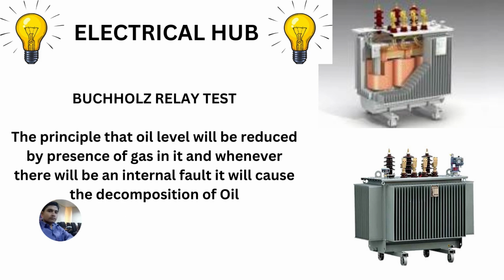Now, let us move towards the Buchholz relay test. Before knowing the test of the Buchholz relay, we should know the operation of the Buchholz relay. How does the Buchholz relay act? Whenever there is a fault in the transformer, then there will be heat, which will be sensed by the oil temperature indicator and the winding temperature indicator.